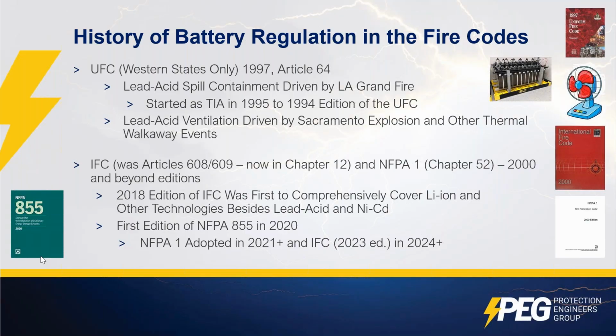But in terms of the evolution, the IFC was sort of the main fire code. If you look at the previous chart, we see that's the most widely used one. There's also NFPA 1. Each of those addresses energy storage systems or batteries in respective chapters. 2018 was the first edition of the IFC to really get a wholesale upgrade. They took the original UFC 1997 section, really went through it from the get-go with a fresh pen and rewrote it to address lithium-ion and not just batteries now, but what they called energy storage systems. And that was published in the 2018 edition.